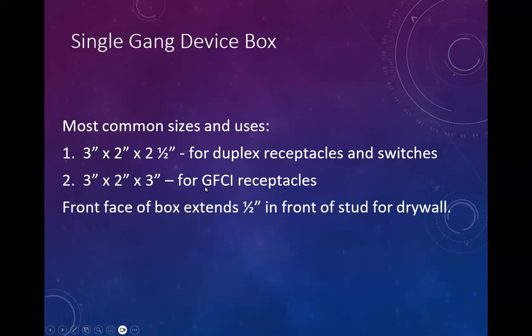If you want to have a GFCI device in the receptacle, a GFCI is a receptacle that is just like a duplex receptacle, but it has some sensing circuitry that will shut things down if there's electricity escaping to the ground. Usually, if water spills onto it, because water is conductive. So that's why we need to have those by water sources. So kitchen countertops, receptacles mounted by the water tap in the washrooms, they have to be GFCI protected. GFCI stands for ground fault circuit interrupt.